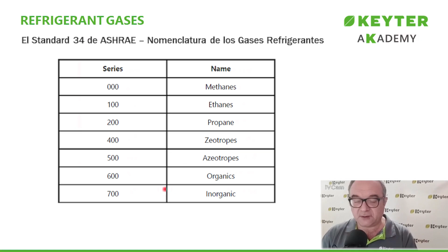If we possess series 0 or series 100, that is, if they originate from methane or ethane, we will possess 4 numbers. This can also be applied to the 200 series, but I have left it as it says there, Standard 34, so as not to distort it. But it would be the 0 series, the 100 and the 200. In fact, there is an interesting case. The 200 we are going to see now has 4 digits. You will say, well, I have seen refrigerants with 2. Okay, those unseen digits are zeros, they are 4 digits, and they are read, or named, from right to left.